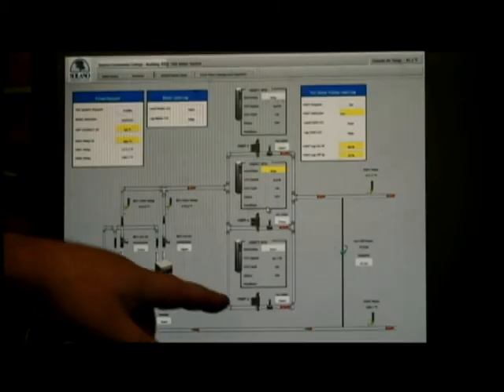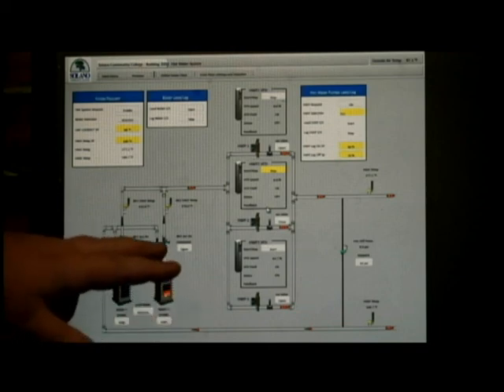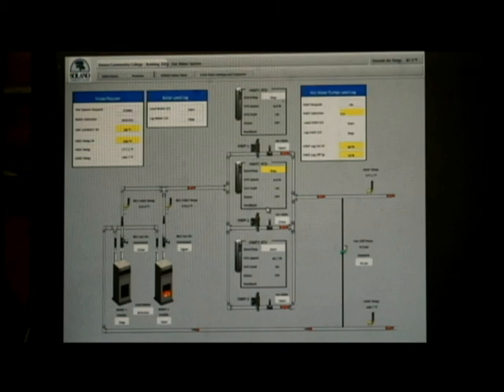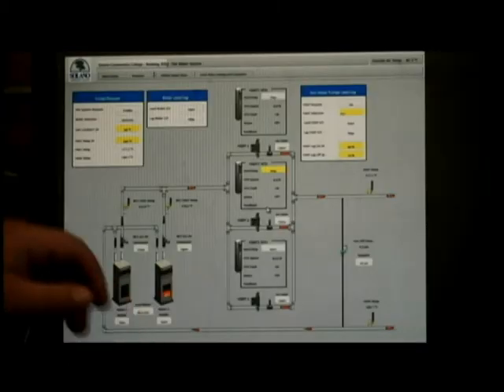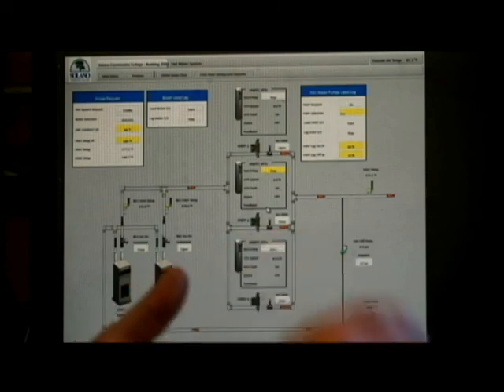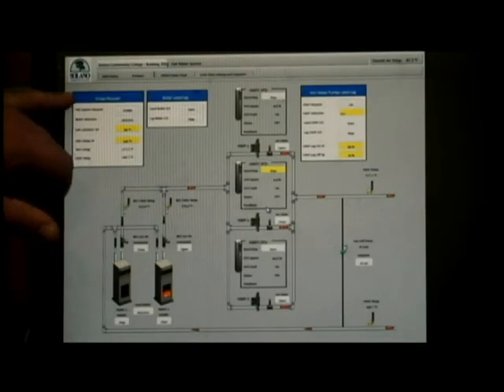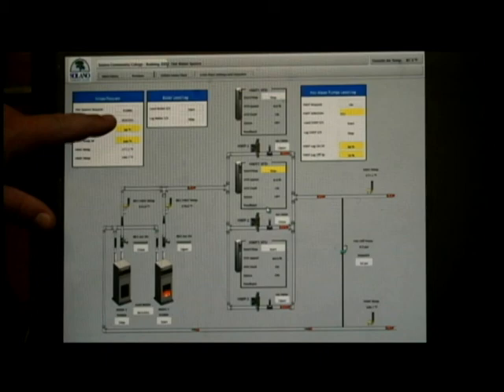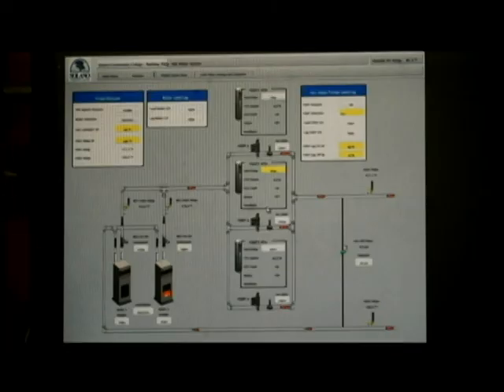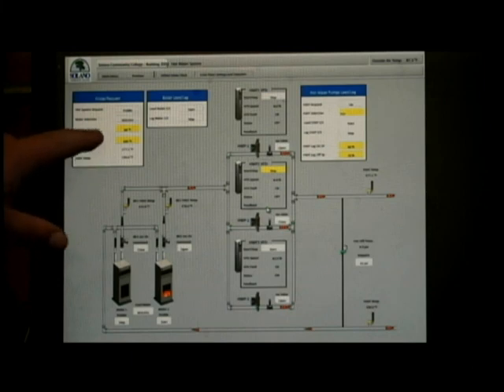Once we have those pumps running, we also open up our associated boiler. There is no lead lag selection on these. Well, there is, but there's only two of them. So rather than seeing the numbers of 3, 2, 1, where we have multiple, more than two pieces of equipment, what we have here under the boiler side in this mode request panel in the graphic is an enable signal, which is based off a hot water system request. It is also based on an outside air lockout. Both the chilled water and hot water systems monitor outside air and will lock themselves out accordingly. For the hot water, that outside air lockout set point is right there, currently set to 90 degrees.